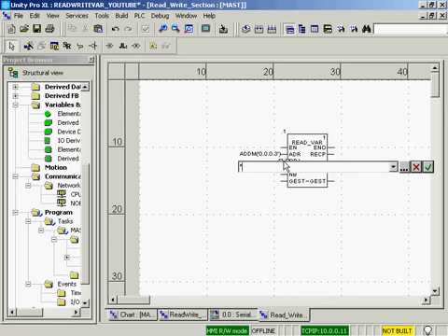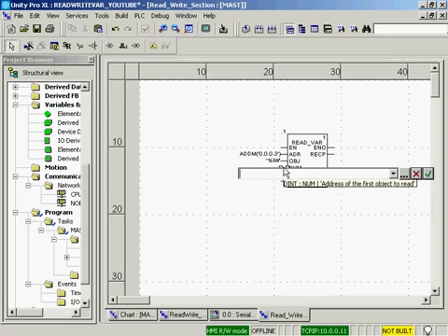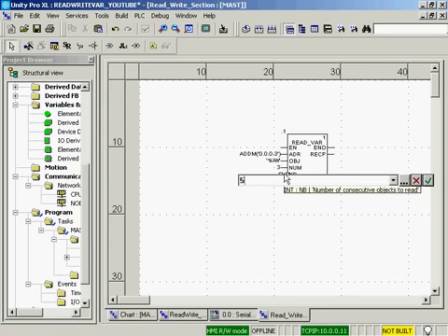So it's open quote, %IW, close quote. %IW is the IEC standard for a 3x register. Now, where are we going to start reading from? We'll start from address 3003. And the number, let's read 5 registers.